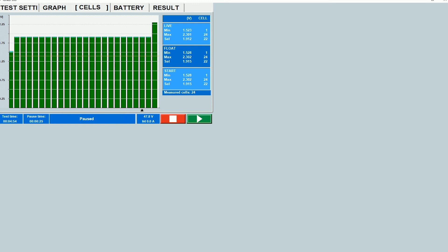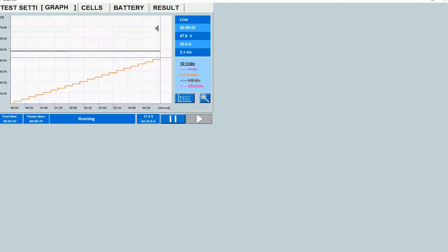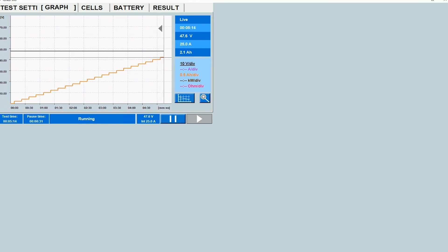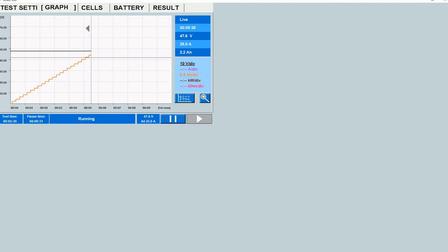To resume the test, once you're done with bypassing the bad cells, you will click on the play button. When you resume the test right now, I'm running a simulation, so I don't really see anything on the graph here. But when you're running a test on an actual battery, if you pause the test and resume the test, look at the graph, you'll see a little bit of a blip on the graph. And that's because when you stop the test, the cells start to recover a little bit, and that causes that little disturbance on the graph. And that can skew your results, and that's why there is a limit on the duration for pausing the test.